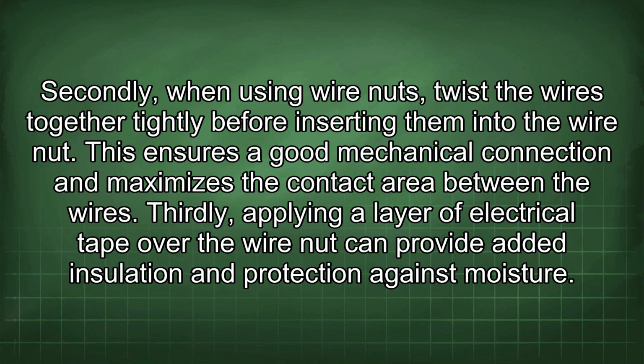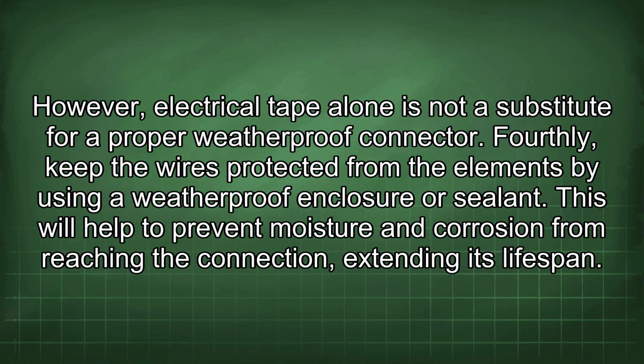Thirdly, applying a layer of electrical tape over the wire nut can provide added insulation and protection against moisture. However, electrical tape alone is not a substitute for a proper weatherproof connector. Fourthly, keep the wires protected from the elements by using a weatherproof enclosure or sealant. This will help to prevent moisture and corrosion from reaching the connection, extending its lifespan.